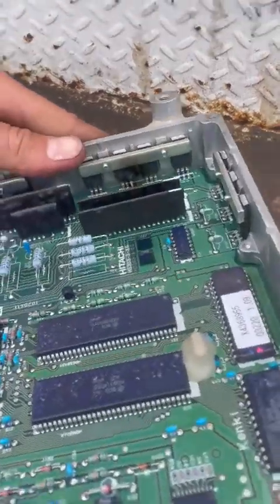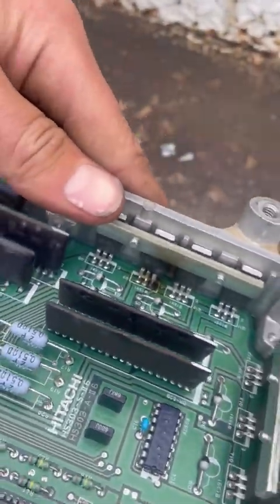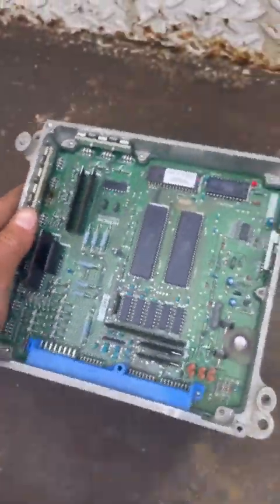And inside the controller, we were able to verify that it is burnt and this controller is bad. I actually had a spare one in the cab from previous years of troubleshooting, so I was able to swap it out and get it fixed. So voltage and resistance, they're important. I would say that's step one, but they don't tell you the whole story, and some of the troubleshooting manuals will mislead you on what you should be looking for. Sometimes you really need to put a load on the circuit to see what's going on.